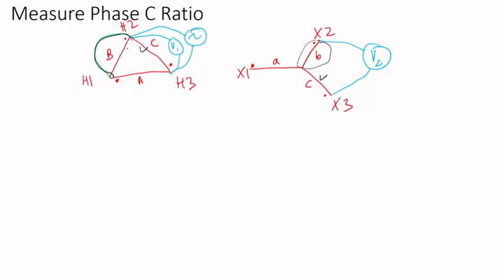That way the flux will be eliminated. Then I can measure from X3 to X2, but really I'm not measuring line to line. I'm measuring from X3 to the neutral, because the B phase is like it's not in the circuit since it's shorted. That phase is shorted, so flux will not be induced. So this is another method to measure the turns ratio when you cannot access the neutral of the Y.